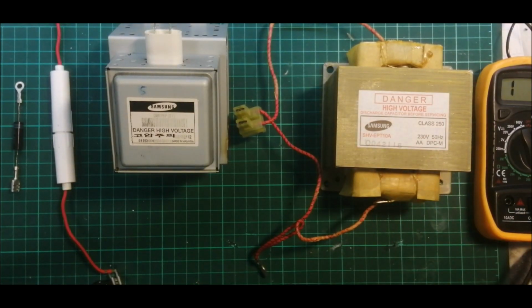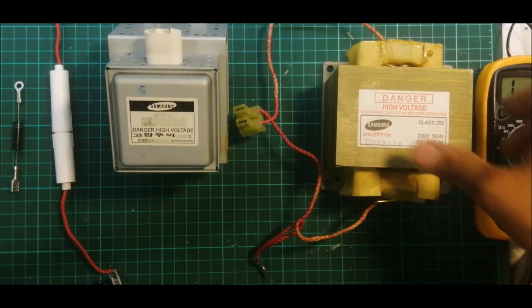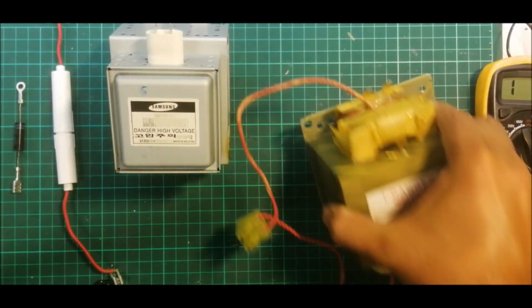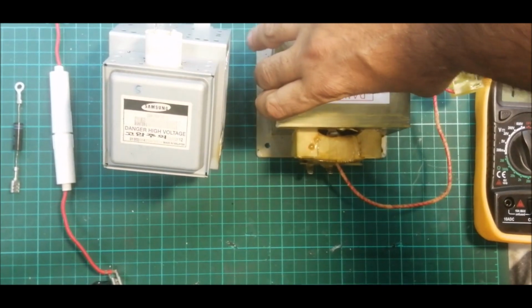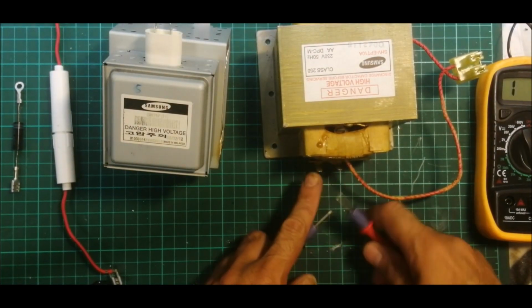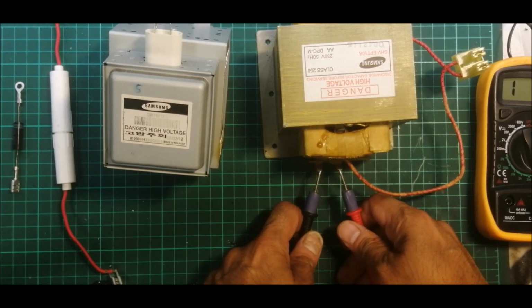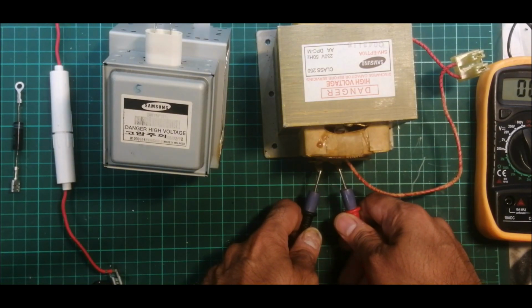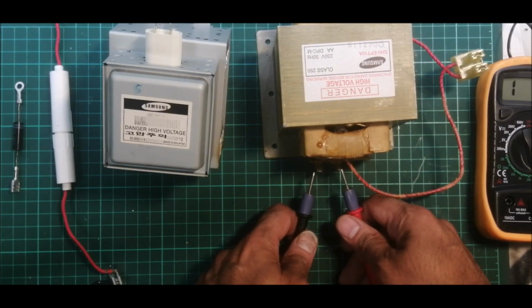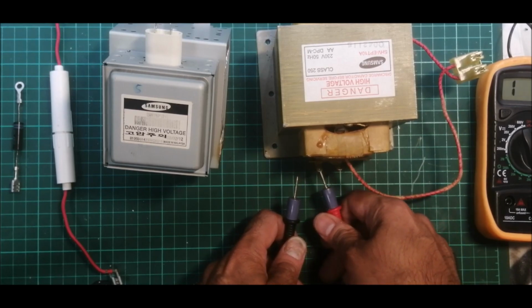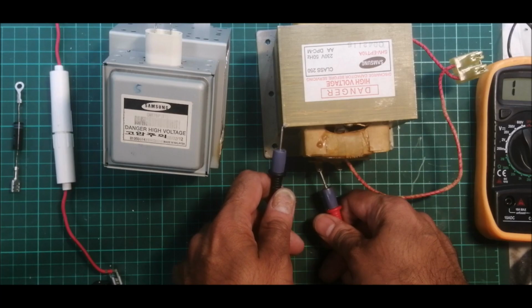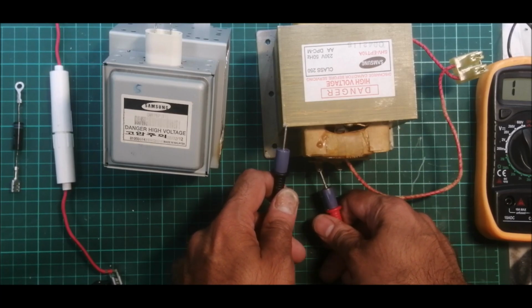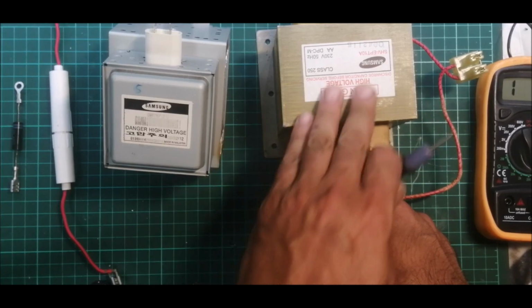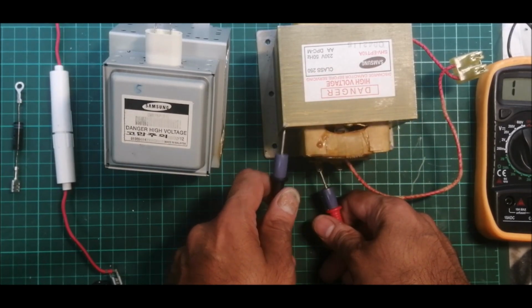So now we go to the transformer. Okay, you got your primary side and you got your secondary side. So we start with the primary side. Okay, so you have two pins coming out here, so you just touch and see, is there any continuity? Yes, that should have a continuity. Now to check whether is there any short circuit, you just touch one of the pins to the body of the transformer. Make sure on the body of the transformer, you can find a place where it's non-coated, okay, because the whole transformer is coated with a thin film for insulation purpose.